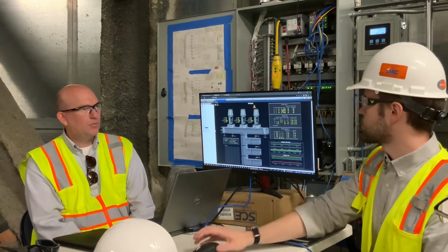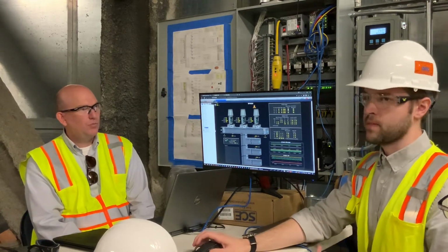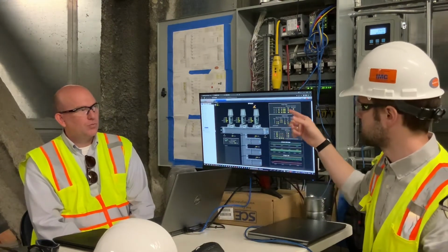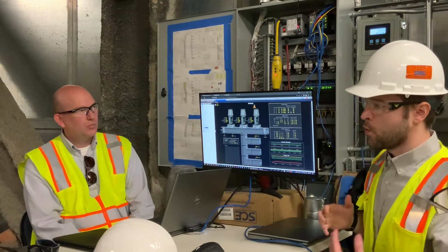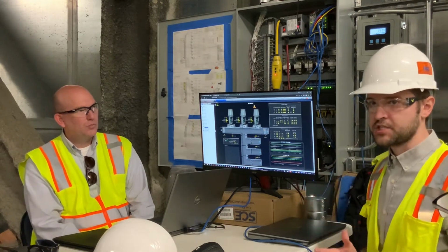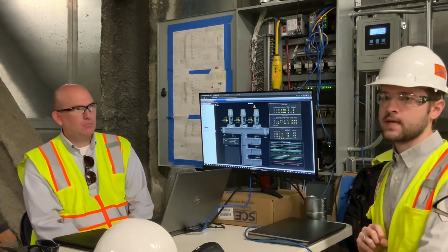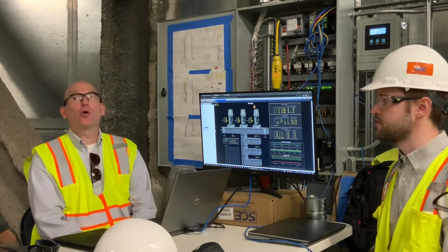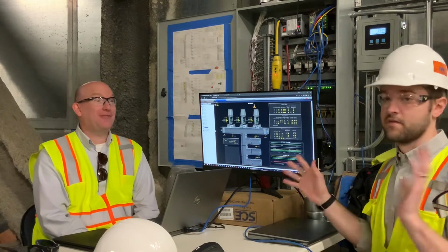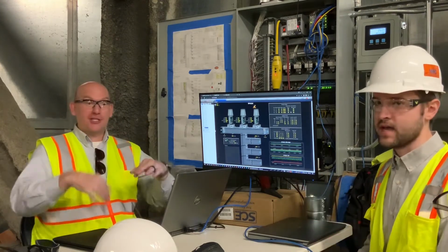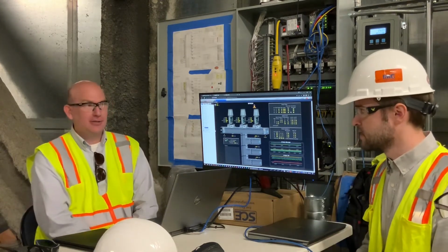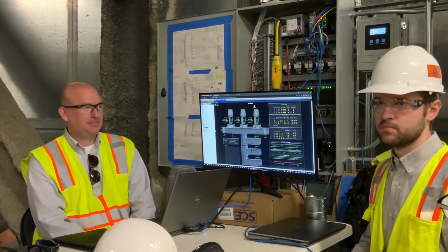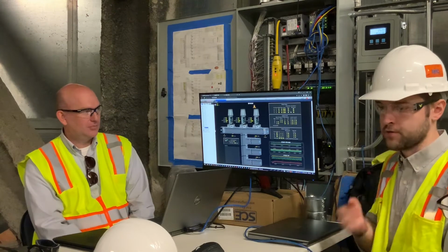If any of these were to fail, or if you needed to put them out of service, you can clear that failure. It might be a little bit hard to read from here, but it says manual clear failure. When the fan fails, there is latching logic in the program that will keep that fan locked out until you have established that fan is allowed to run again. Or if all of them fail, it'll release them all and try to start again. The idea is that, if anything were to go wrong, they want you to get eyes on it before it just goes and tries to run it again anyway.